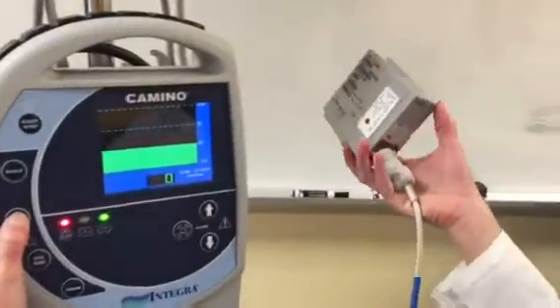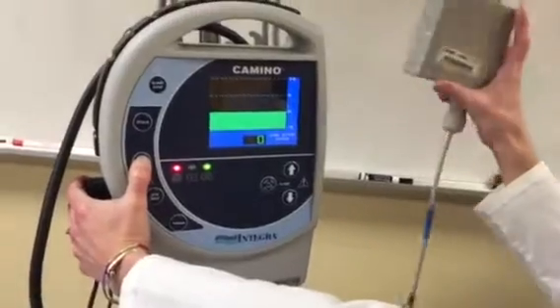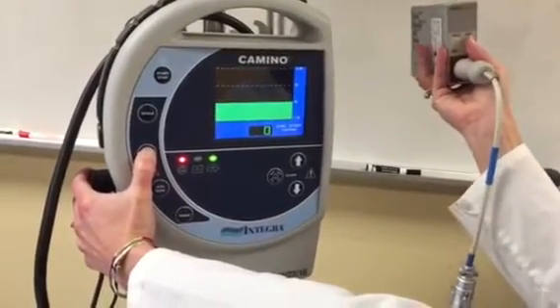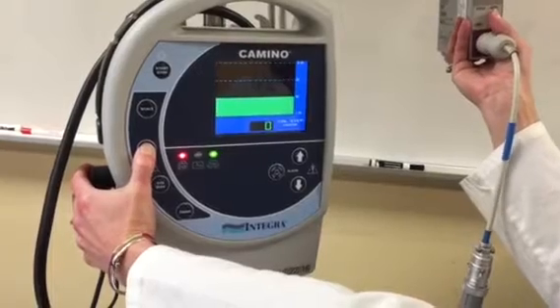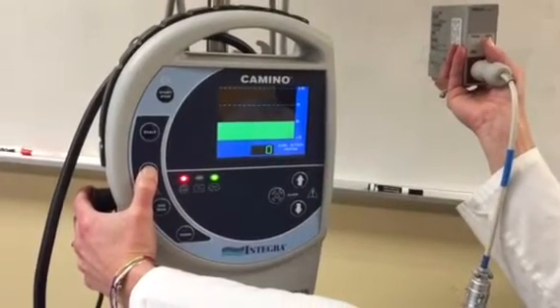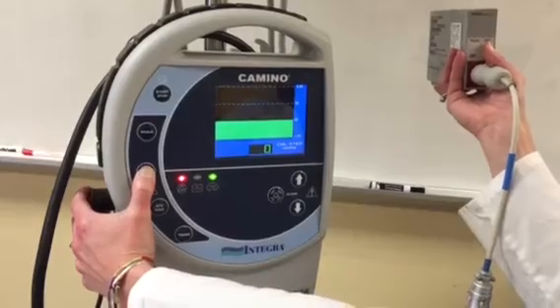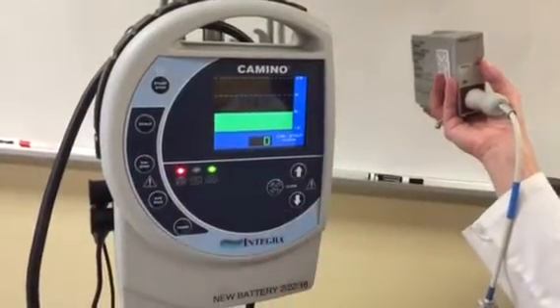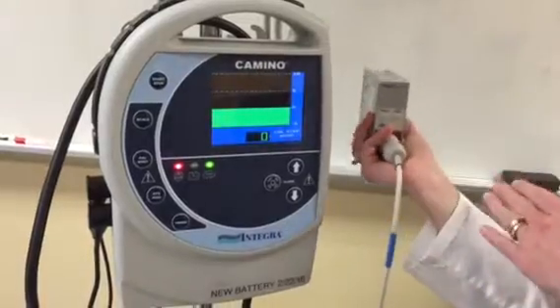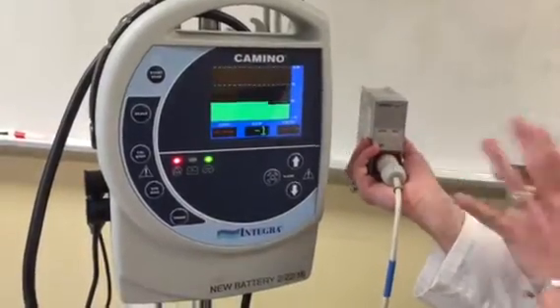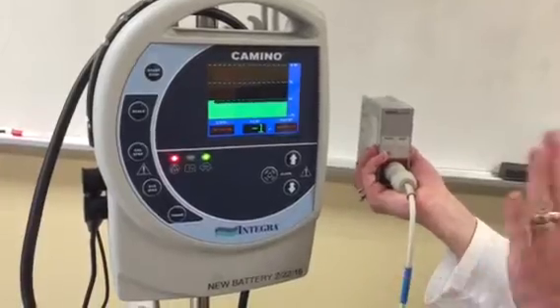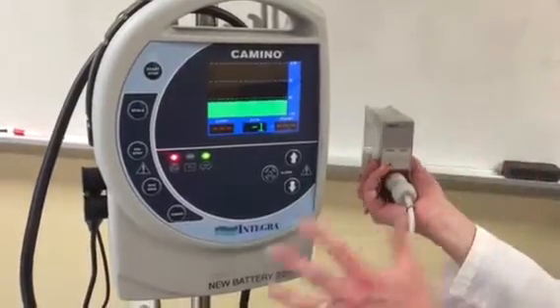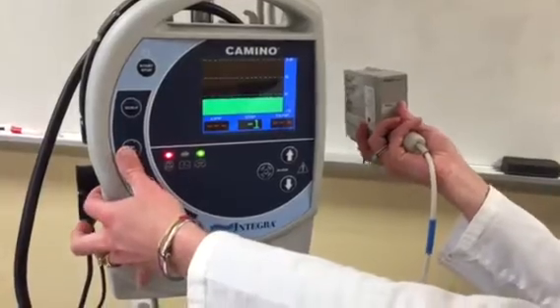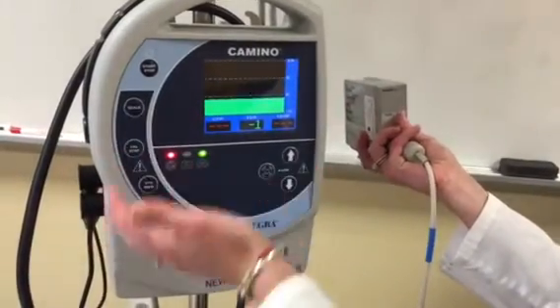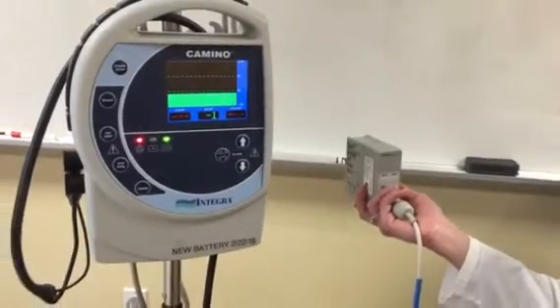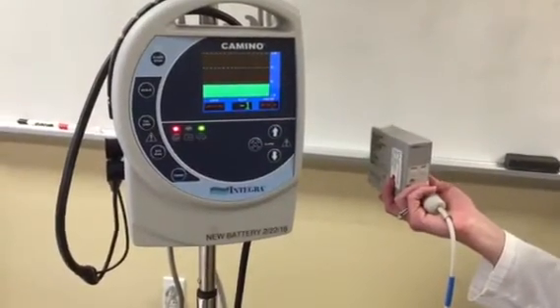The other thing you're going to do at the same time at the bedside monitor, so you either need to have your Camino on the same side or you need 2 sets of hands. You're going to push this 0 button right here, hold it down until the Camino goes through its calibration steps. You'll know it's done because then it goes right back to normal ICP monitoring. Now, this has a potential to cause a little bit of confusion. We use the 0 button for the calibration, but again, remember, calibrating does not equal zeroing. It's just the button we need to push to calibrate the Camino to the bedside monitor. And then once it starts reading the ICP again, you're set. So that is the entire setup for the ICP catheter only.